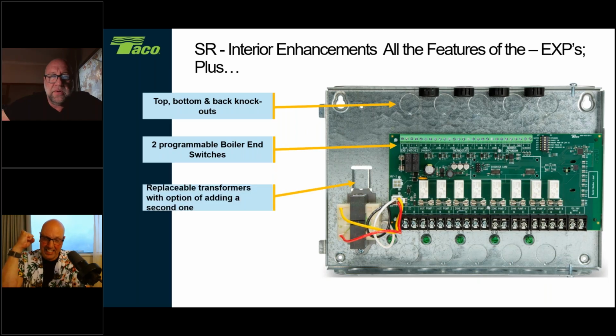We have also made the transformers replaceable. Okay, now they were replaceable before, but unfortunately the transformers were riveted on the board, all right, on that backboard there. So now it's a single screw that you'll see here and a tab that hooks in. And we put a Molex plug on them. And here you're looking at a switching relay. The switching relay comes with a 20 VA transformer. We do have part numbers for a replacement 20 VA, and we also have a part number for a 40 VA. Or you want to add and drop in a 40 to the upper space here if you are looking at those power hungry thermostats that are out there.